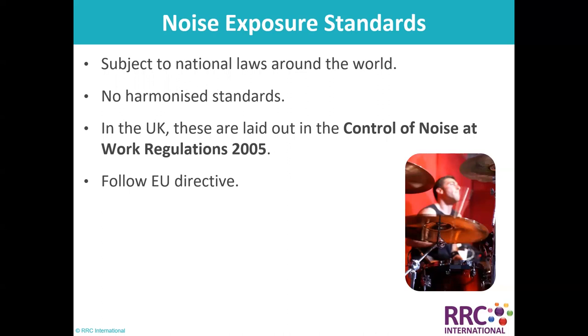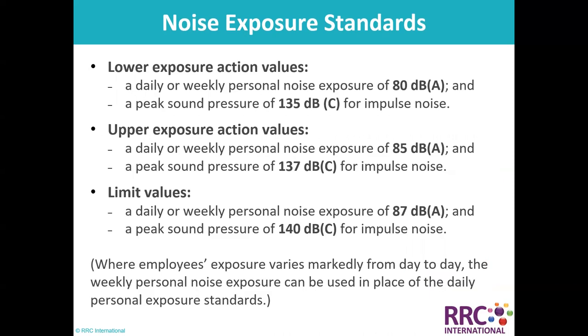Standards are subject to national laws. In the UK, they are laid out in the Control of Noise at Work Regulations 2005, following the EU Directive. Lower Exposure Action Values are a daily or weekly personal noise exposure of 80 dB(A) and a peak sound pressure of 135 dB(C). Upper Exposure Action Values are a daily or weekly personal noise exposure of 85 dB(A) and a peak sound pressure of 137 dB(C) for impulse noise.